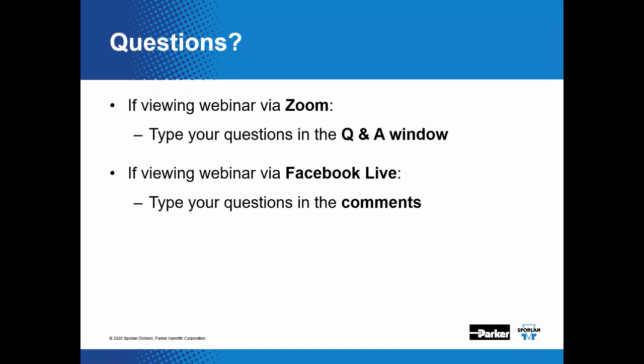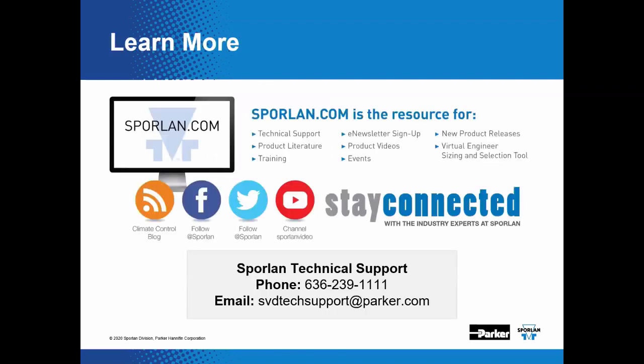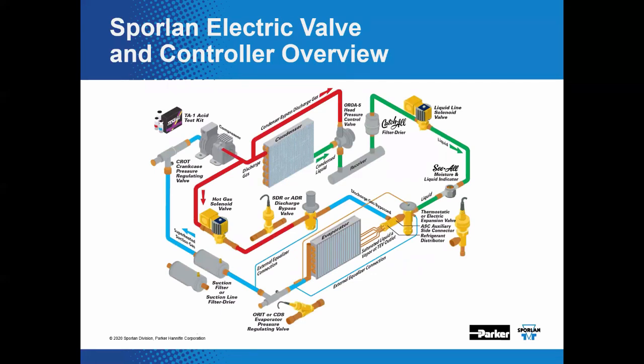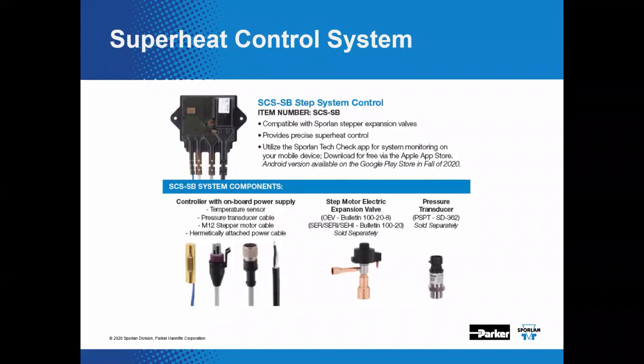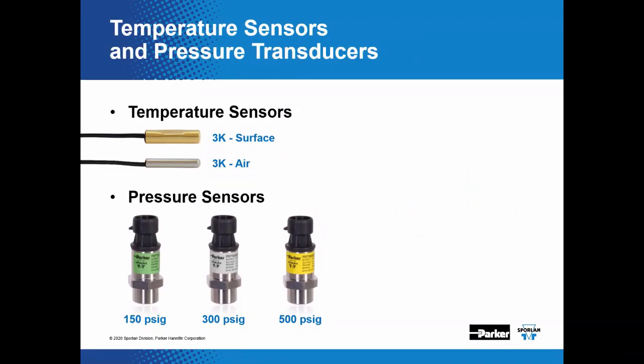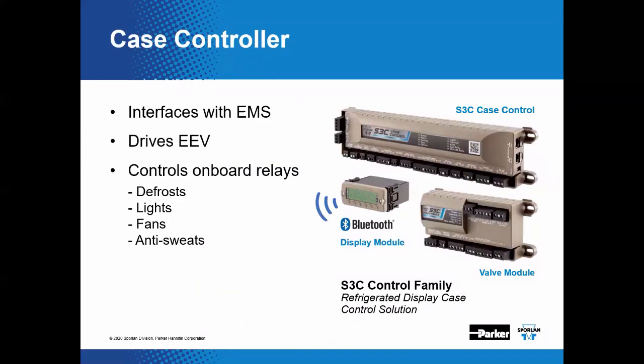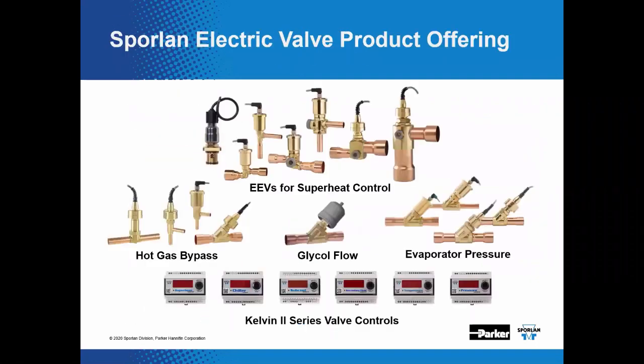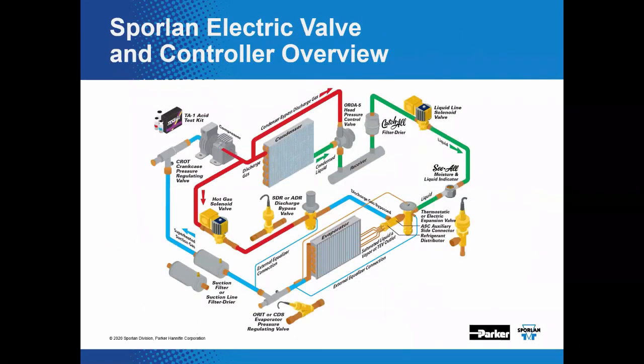So the question is, on a power failure, does the valve stay at its last position or does it drive shut? Well, here's what I know about that subject, if you don't mind, Jim. Go. All right. So the valve itself, when it loses power, is not going to move. It needs electricity to make that happen. Now, some controllers have an actual built-in battery so that they can shut that valve upon failure. If the controller has that, then yes, that valve will go shut, because that's the way they're programmed. However, if they do not have that battery backup, then they cannot go shut. However, if I remember right, many controllers will, on a re-engagement of power, reinitialize that valve so that it knows where it's at, so it can then start up and start functioning properly.